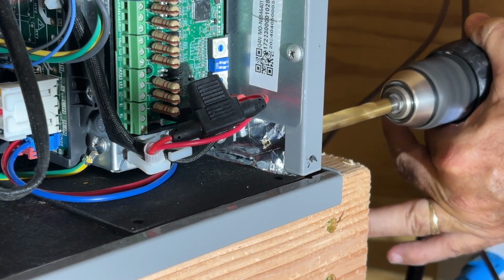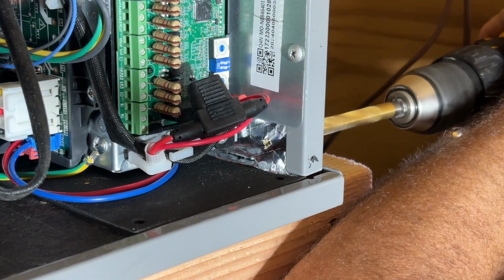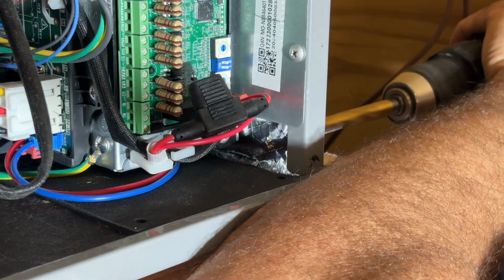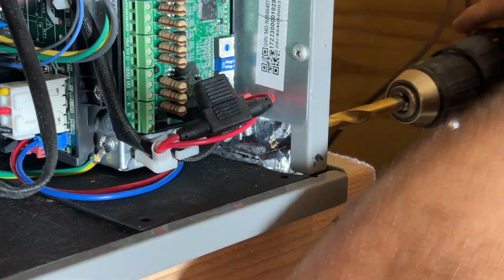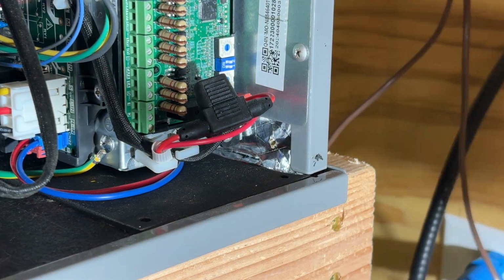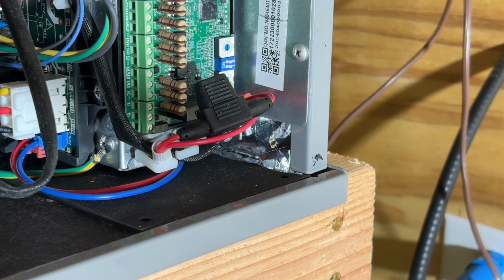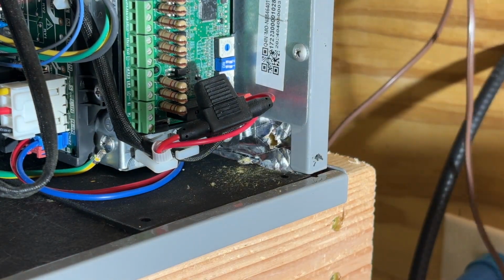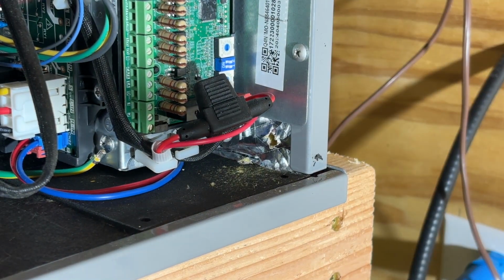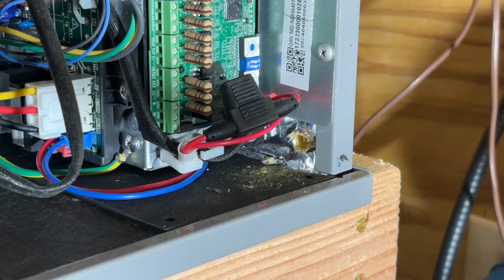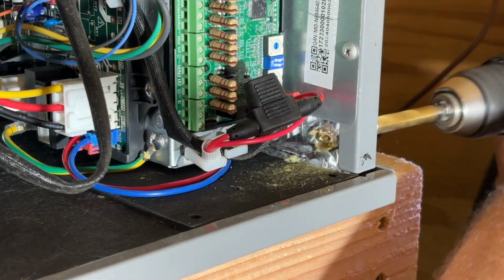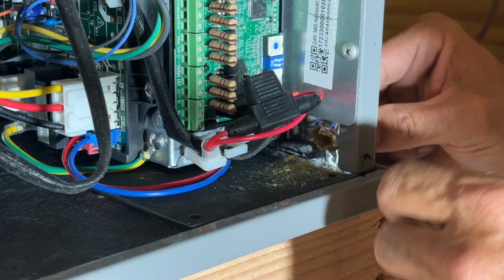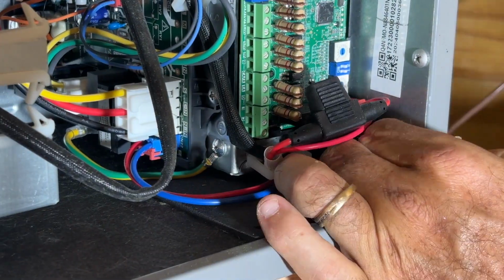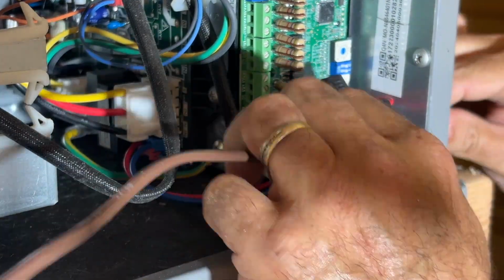You're going to see me struggle here with this hole. My bit was very dull, so I had to drill several pilot holes to get the 3/8 inch bit through there. I believe it's a 1/4 inch wire grommet that I ended up putting in there, and it required a 3/8 inch hole, and my drill bit just needs to be sharpened. But anyways, when you're drilling this stuff, it's not going to tell you in the book where to put your hole, how to drill it, how to do any of this stuff. So you just have to pick a spot. Don't damage anything on the inside as you drill your hole. Just be careful and get your thermostat wire through there.